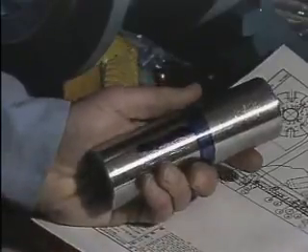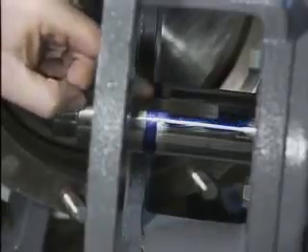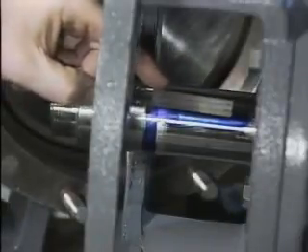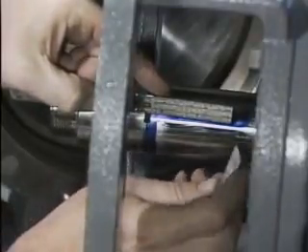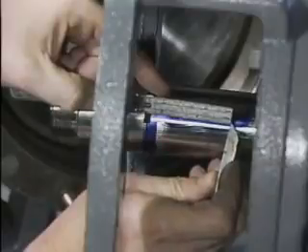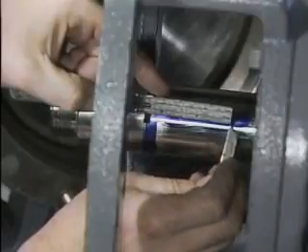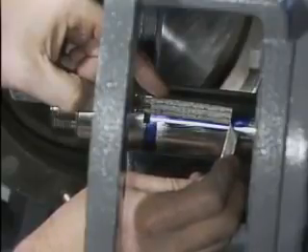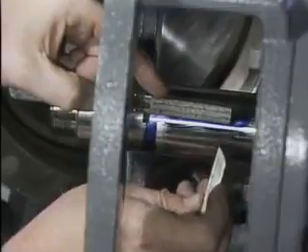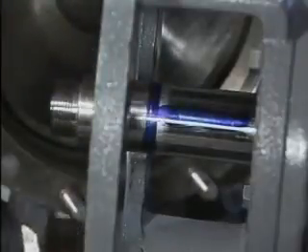Of course, there are some exceptions to the general procedures that we've just seen. For one thing, seals are not always mounted on shaft sleeves. A variation in the measurement procedure is associated with the location dimension for an outside seal. This type of seal is mounted outside the casing that's being sealed. So the second scribe line, which is used as a reference line for properly positioning the rotating ring collar, is made in the direction away from the impeller end of the shaft.